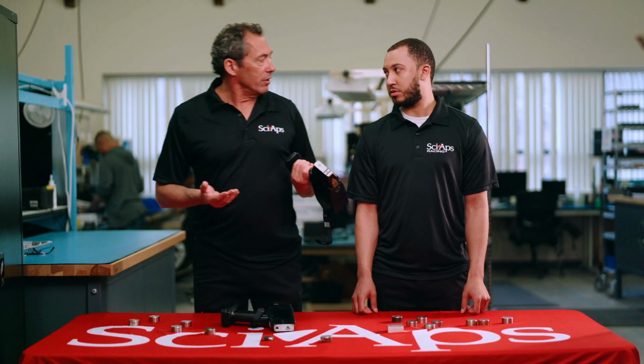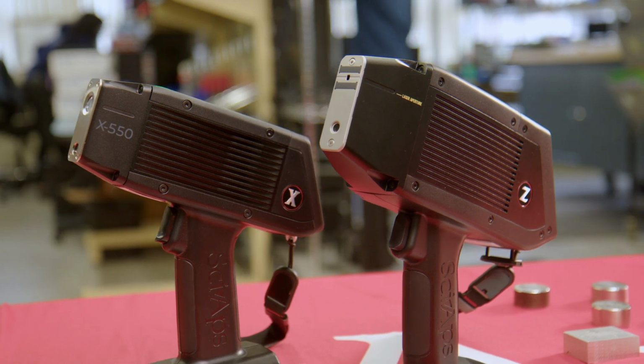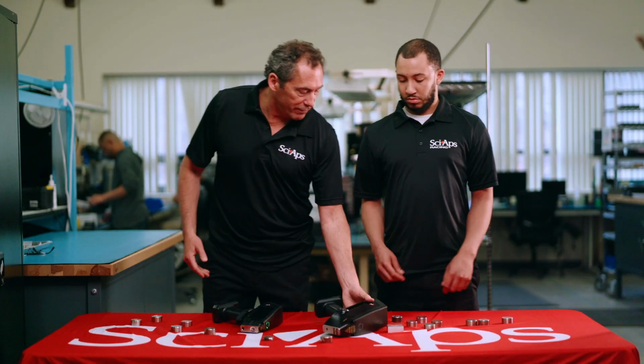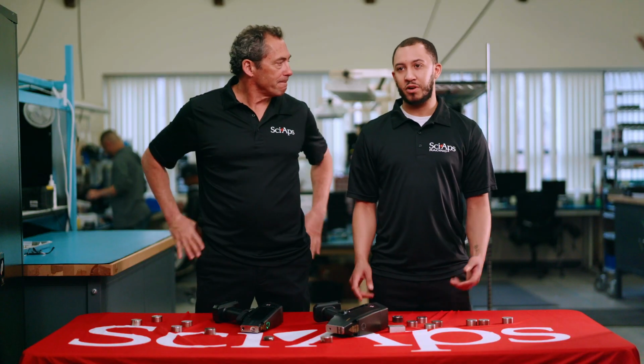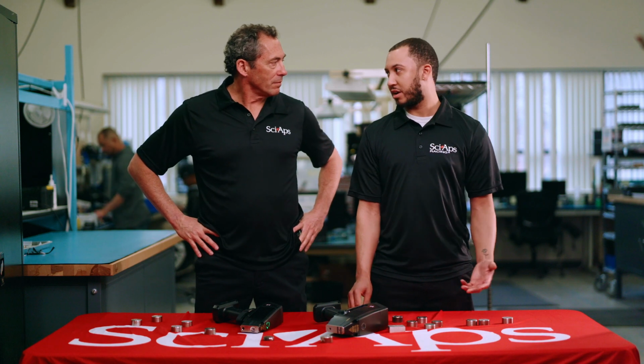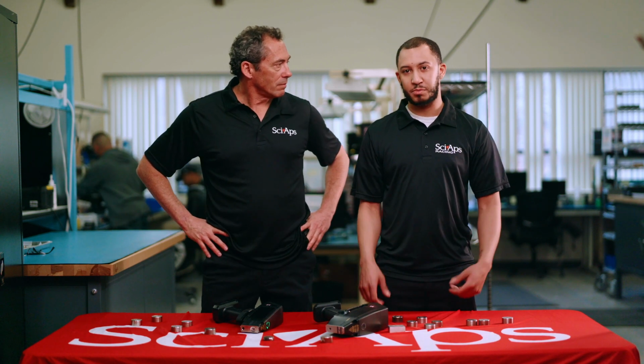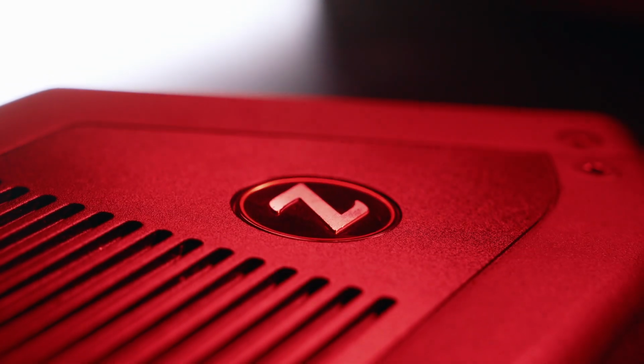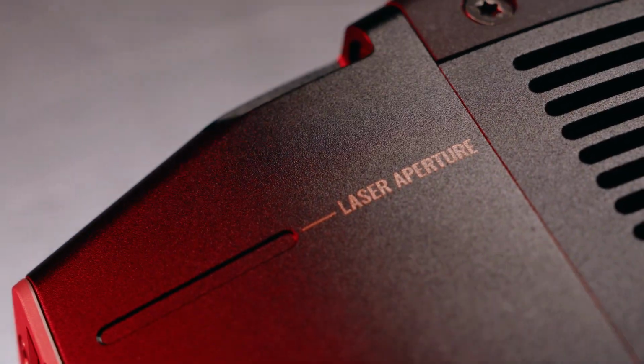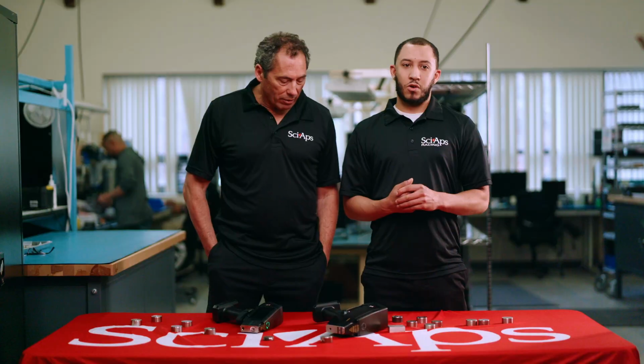You work mostly on the LIBS or the laser device, right? Do these take longer to service than the typical X-ray device? I wouldn't say typically longer, but once you open the unit up and start taking things apart, certain little parts you have to realign just from removing a specific part. If you don't have to replace a laser, a typical repair is like what, a leaky argon or bad board or something? Cracked splatter shield, things like that. That wouldn't take typically as long as an alignment would take.